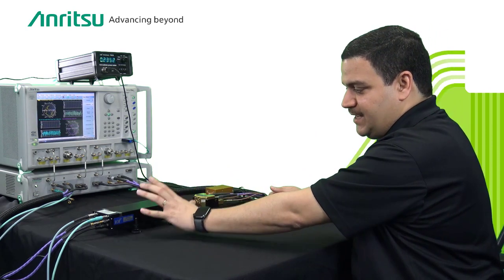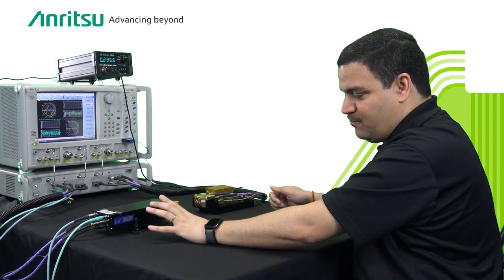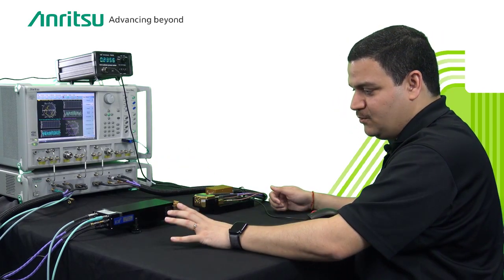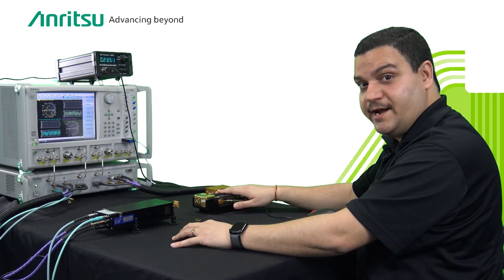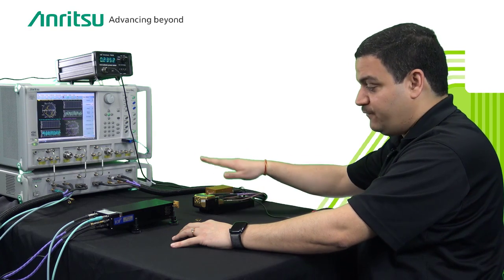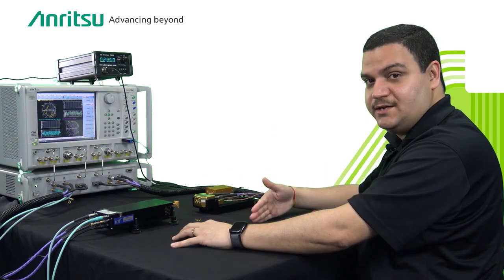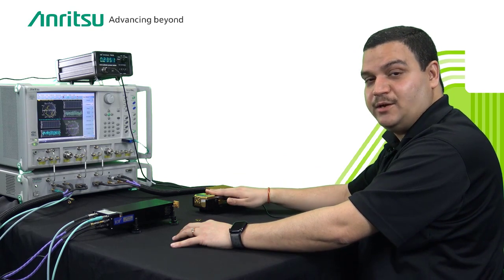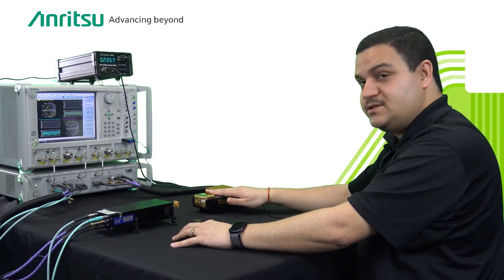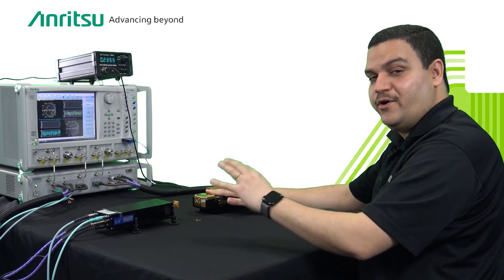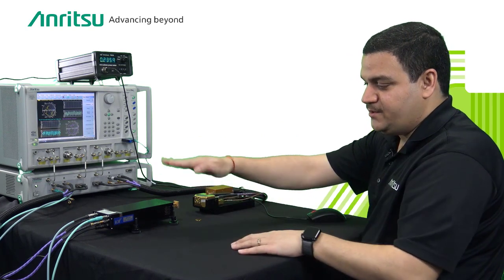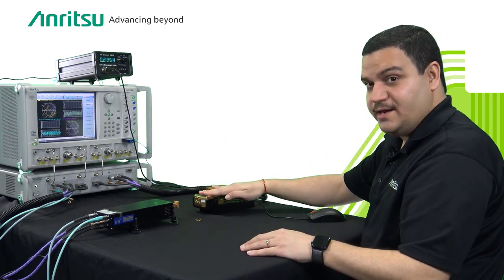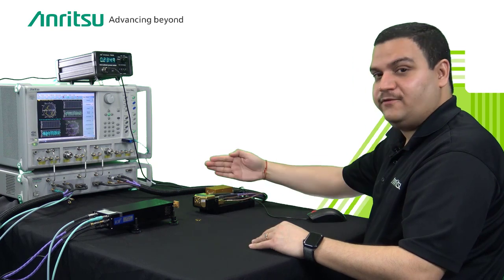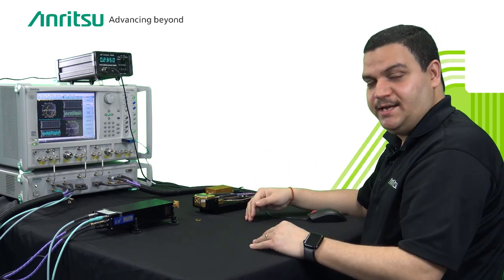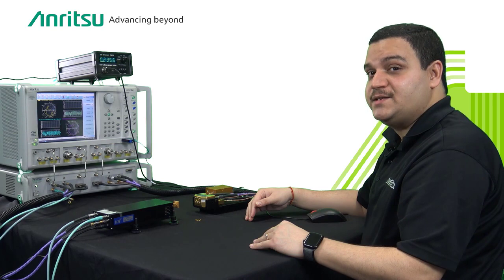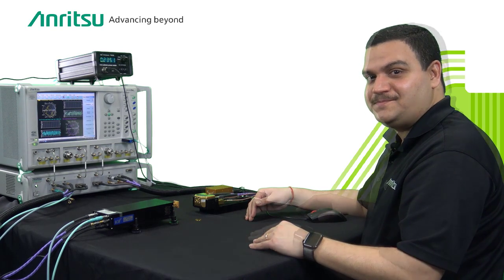However, since this combination can now work, you could have one side VDI having an E band module, D band module and G band module. On the receiver side, since this one covers from 70 GHz to 220 GHz, you need not change the setup at all, which means now you only need 4 mmWave modules: 1, 2, 3, and this one is the 4th one, which covers right from 70 GHz to 220 GHz. This is a very interesting solution.